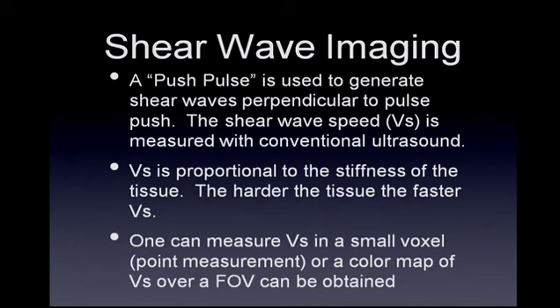For shear wave imaging, a push pulse is used to generate shear waves perpendicular to the push pulse, and the shear wave speed VS is measured with conventional ultrasound. VS is proportional to the stiffness of the tissue—the harder the tissue, the faster the VS. One can measure VS in a small voxel as a point measurement or use a color map of VS superimposed over the field of view to get a wide field-of-view image of shear wave velocities.